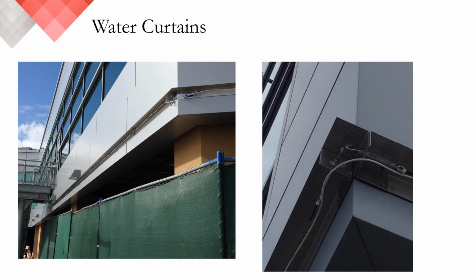We see water curtains being employed throughout airports as well. Passenger terminals are typically designed with an overhang to provide shelter and storage for vehicles and equipment. They're also designed with a lot of glass to provide views out onto the tarmac up above. Being directly below the passenger boarding area requires safety measures are in place to keep windows in the terminal from imploding during a fire. Water curtains are just one of the life safety measures employed.